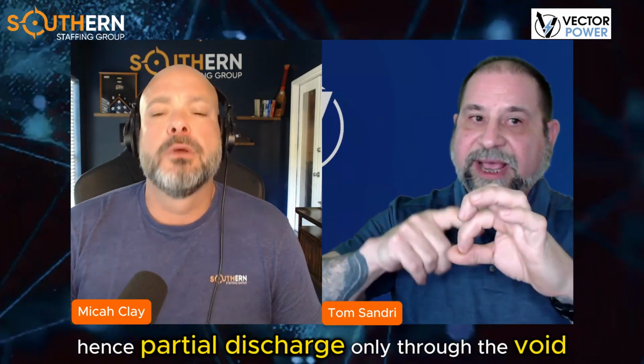So as the potential rises, the surrounding material can withstand it, but charge builds along the void, and then it can no longer sustain, and it discharges through the void. Hence partial discharge, only through the void, not through the whole insulator. But if this occurs and continues to occur, it's going to grow the size of the void. It's going to start to go into what we call an electrical treeing or growth. And at some point, it's going to basically provide a current path through the insulator, and you're going to have a total failure at that point.